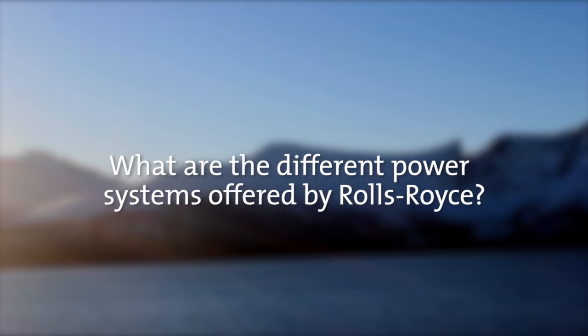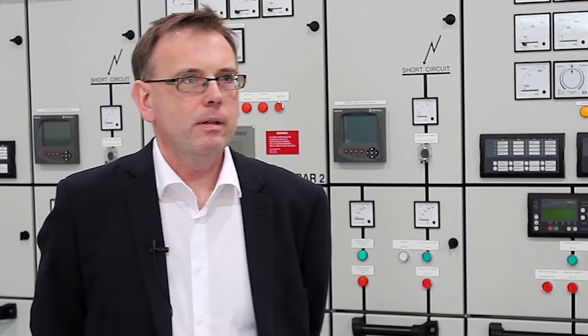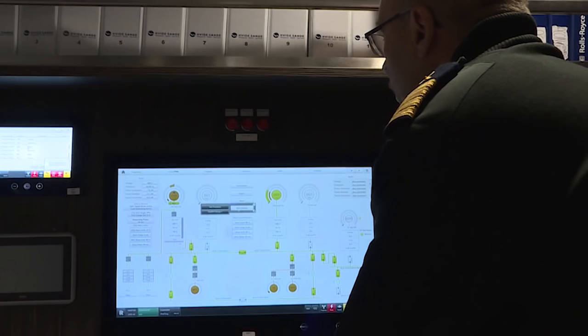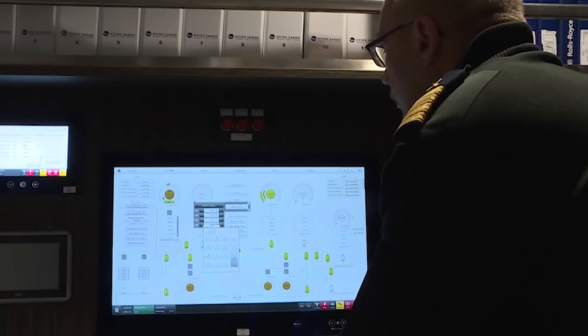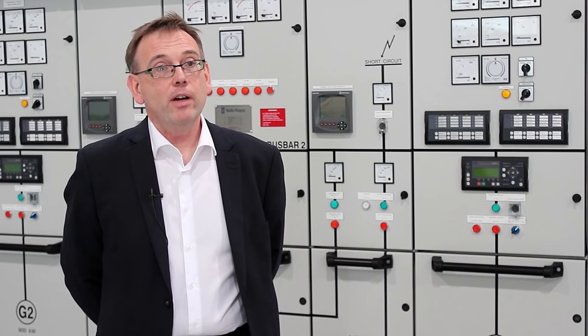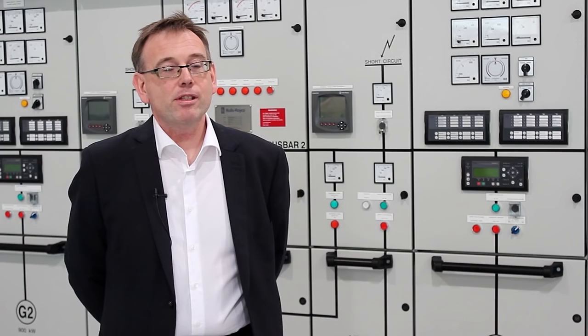In Rolls-Royce we have different power system topologies. The SAVe CUBE is one variation of these power system topologies, where we arrange consumers connected to a DC switchboard, instead of the traditional way of doing it where you have an AC — alternating current — switchboard. That enables variable speed generation on the gensets, which enables lower fuel consumption at part load. It also enables quite a bit of reduction in vibration levels on the vessel.